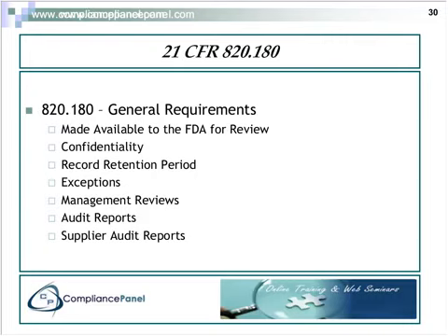So under Freedom of Information, if you have a supplier, for instance, that's supplying you with a finished device that's an accessory to your device, you can apply to the FDA to say, I would like a copy of their last establishment facility audit, and you can obtain that. So anything that you feel is confidential must be marked that way, or it can become part of public record.